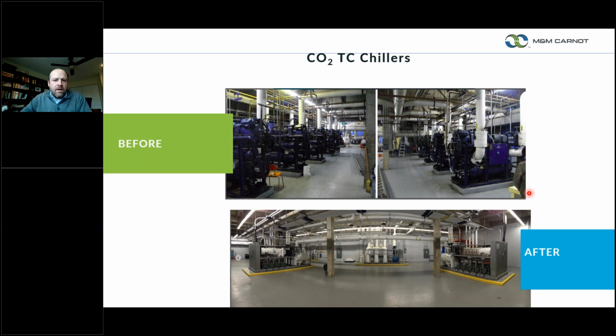So this is an introduction of the data center cooling equipment that we have, but while we were developing that data center cooling equipment, our business was primarily in industrial refrigeration. And this is one of our first applications, where there was a hockey rink up in Canada, so a big ice rink. And next to that ice rink was the library and also some swimming pools. But the old ammonia screw or reciprocating compressors that we had, shown up on the top, were approaching end of life. And so we stepped in with a CO2 based solution where we could make the ice in the hockey arena, but also in this application, we had 5 heat exchangers that were able to create different temperatures to be reused throughout this facility.